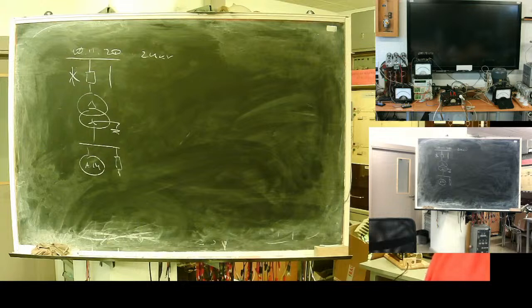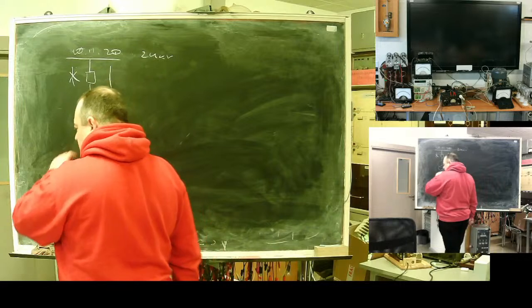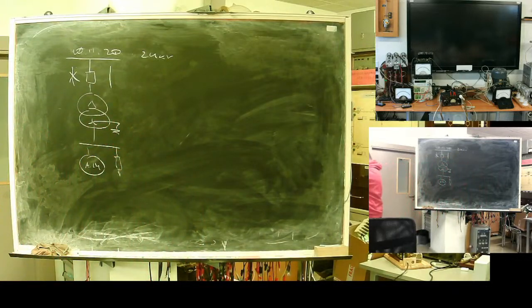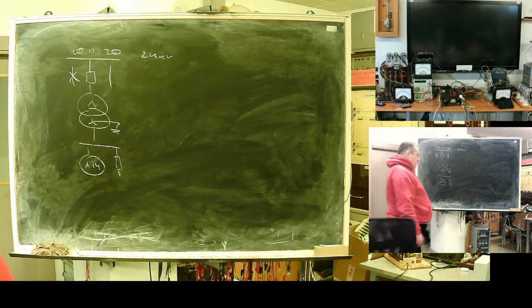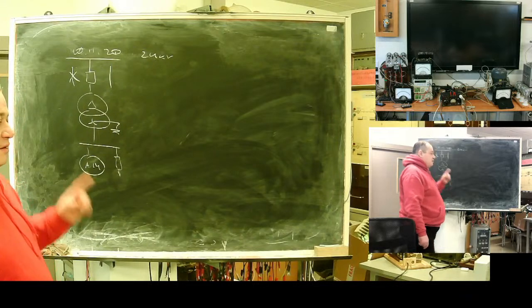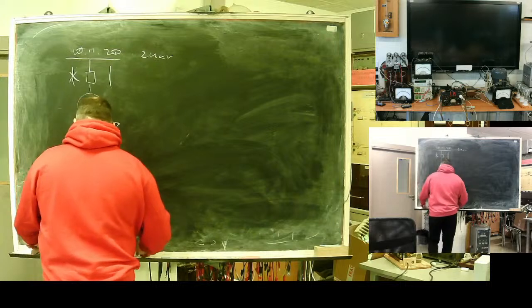My practice for a really important case: you need a negative sequence protection relay. Maybe one is a start. Voltage asymmetry relays. Okay, voltage asymmetry relay. But for a really important thing, you need something like this Siemens and a negative sequence overcurrent relay. But okay, first, how can we model such a fault?